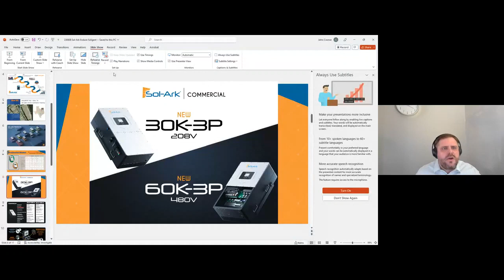There really aren't that many 208 3-phase out of the box inverters on the market. Most of the commercial industrial inverters on the market are 480, and you will lose power or have to use an inefficient transformer to get down to 208 3-phase. Alternately, you could take a bunch of residential single-phase inverters and stack them in groups of 3 to get 208 output. And there's slightly more you can do with that if you want to get into imbalanced loads.